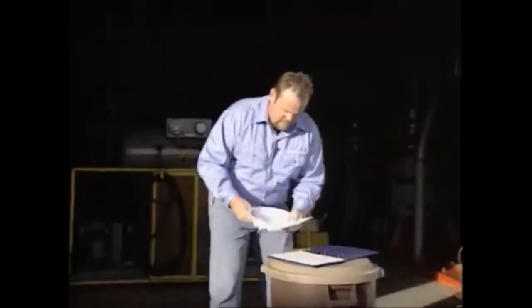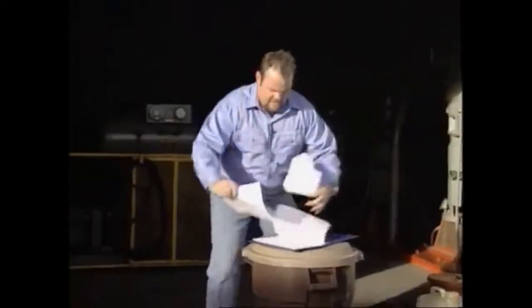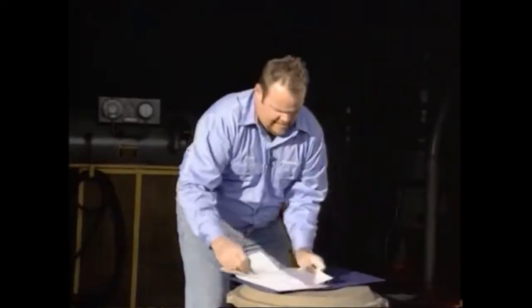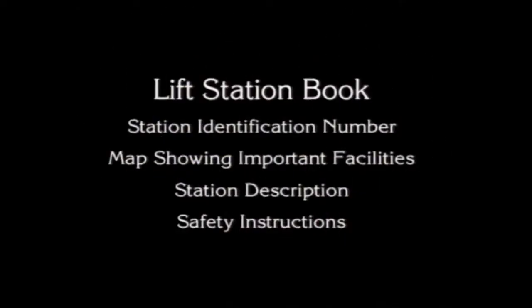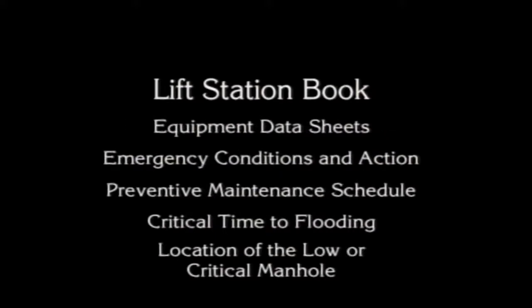The station book is a loose leaf binder so that information can be easily kept up to date. The lift station book should contain the following information: station identification number, map showing important facilities, station description, safety instructions, equipment data sheets, emergency conditions and the action to be taken when an emergency occurs, and the station preventive maintenance schedule. The critical time until homes or streets are flooded must be included. If an auxiliary power generator is not standard equipment at the station, the procedures for obtaining a generator should be located in the station book. Also included are procedures to electrically isolate the lift station and to connect a portable generator.